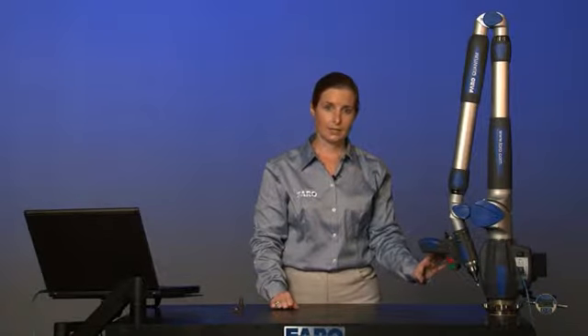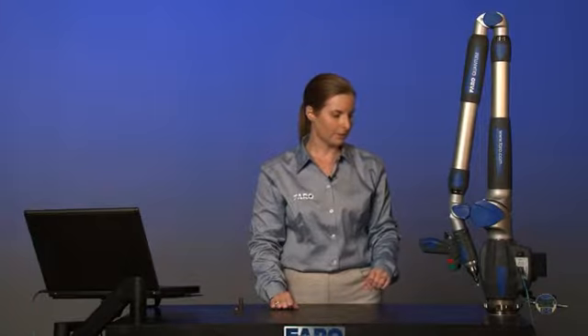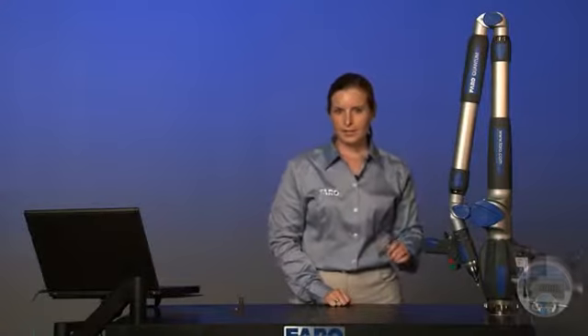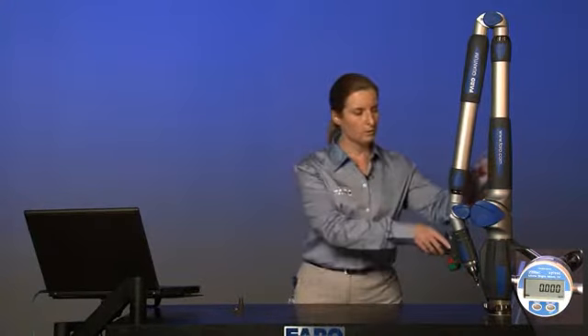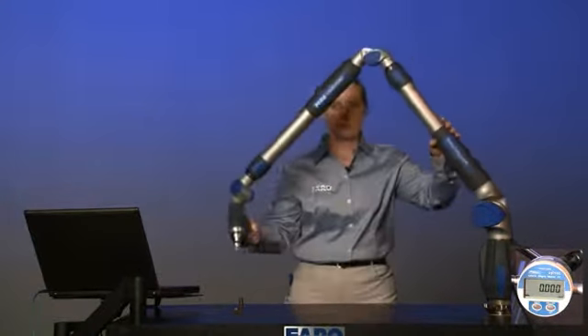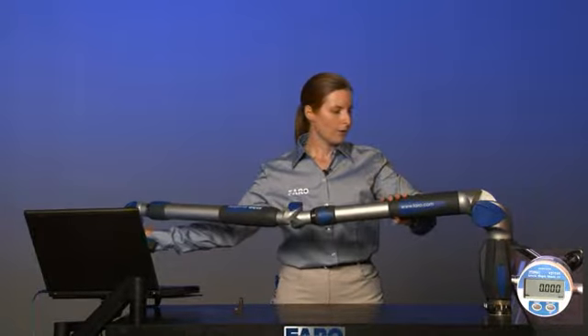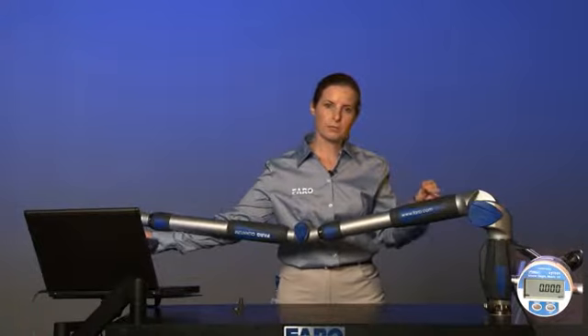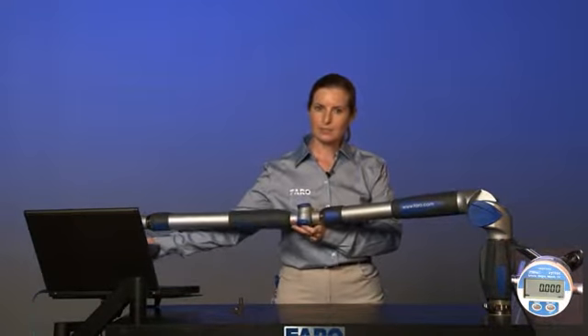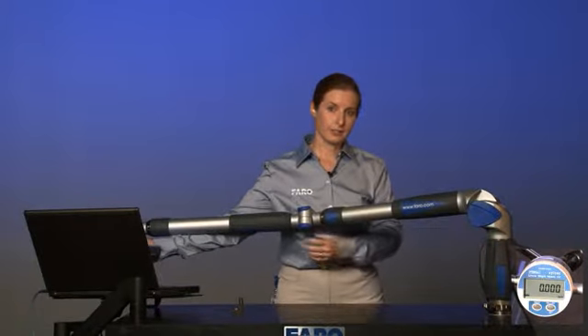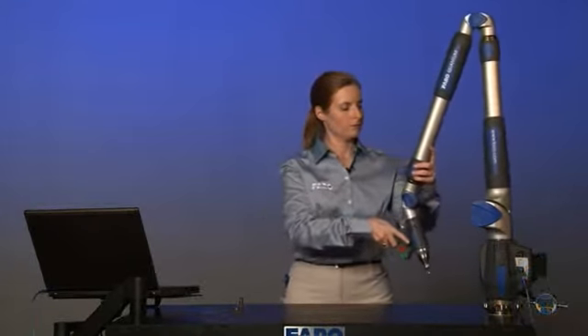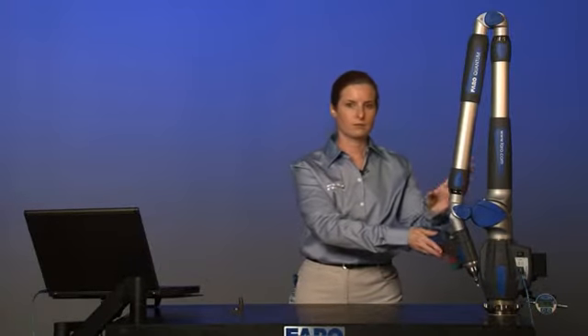If you have any question to the stability of the arm after doing that, you should then go to a dial indicator. We've got a dial indicator set up on the arm just to the left of our setup. With the dial indicator pointed to the base of the arm, you want to move the arm in the opposite direction of the dial indicator. By pulling the arm in the opposite direction, we would see the most movement on the dial indicator. So if there's any instability in our setup, it would now be registering on the dial indicator. With these two checks, you can verify that your setup is secure and accurate.